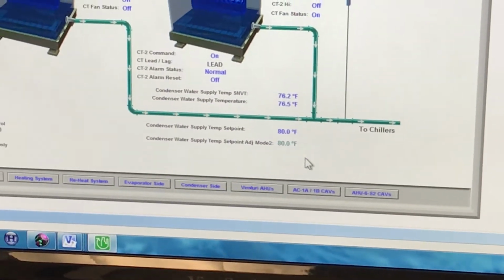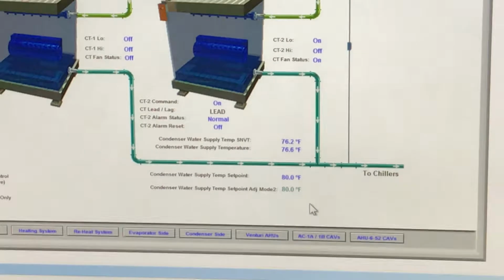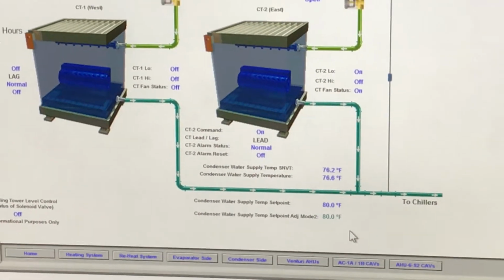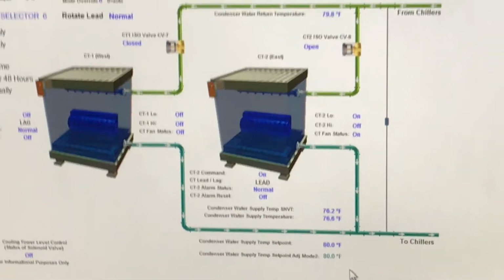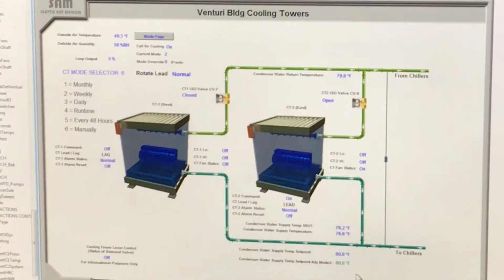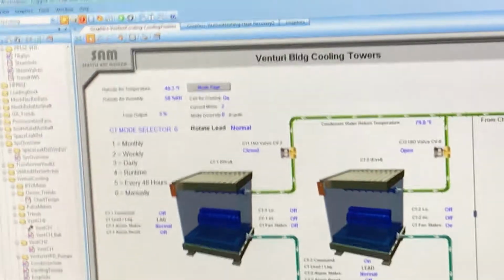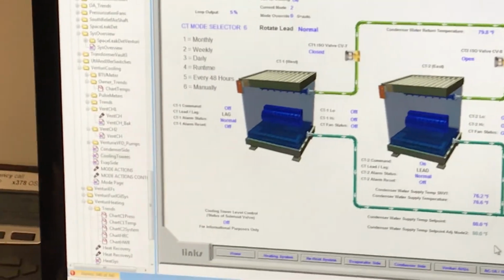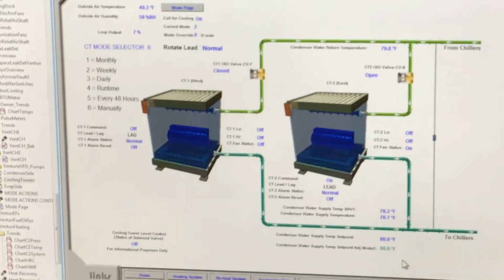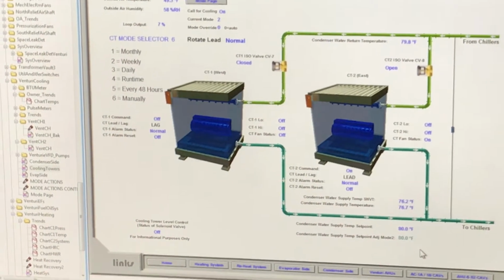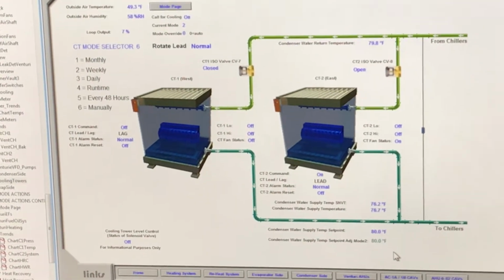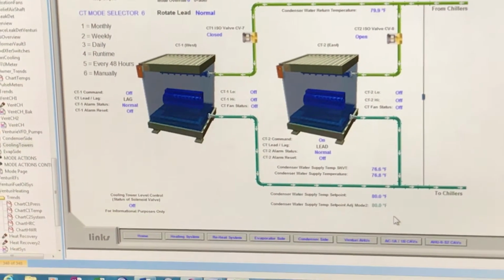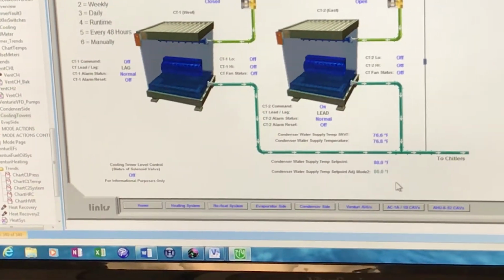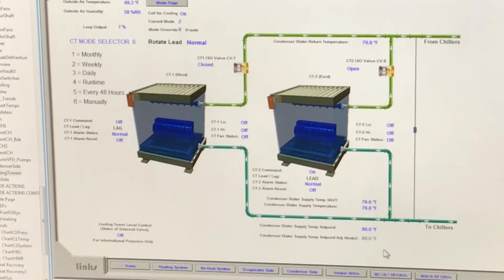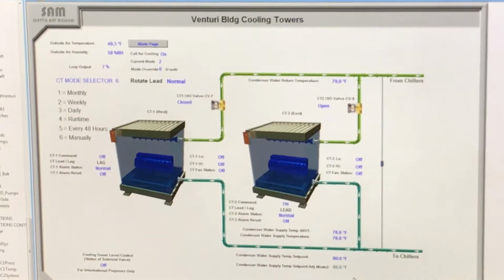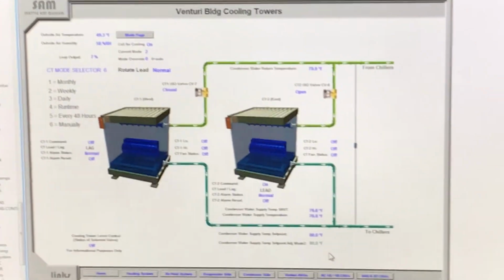Even when it's adjustable, that set point is actually kind of dictated by the chiller. When you are in cooling mode, the chiller would prefer a range of 65 to 85. So the set point is determined based on your outside air temperature, calculated within the range that is okay for the chiller.